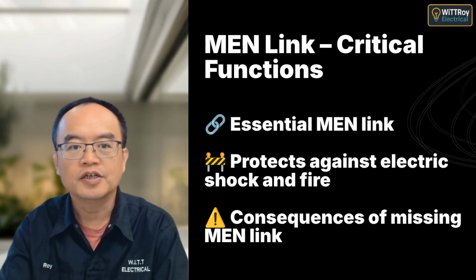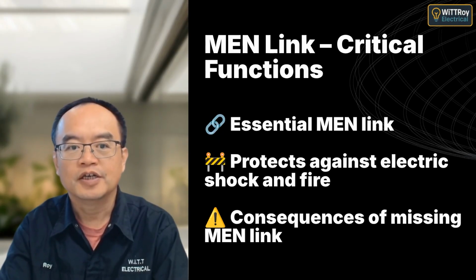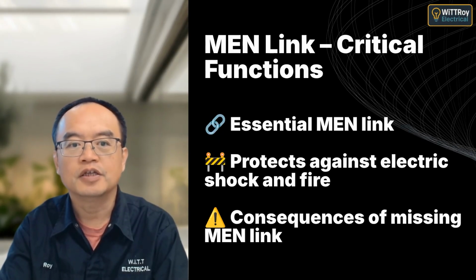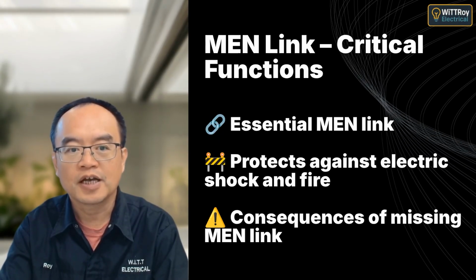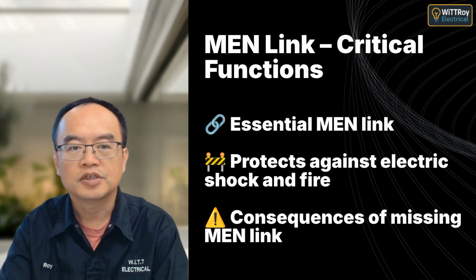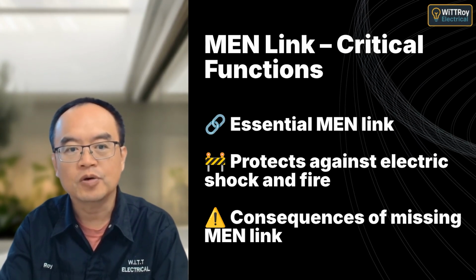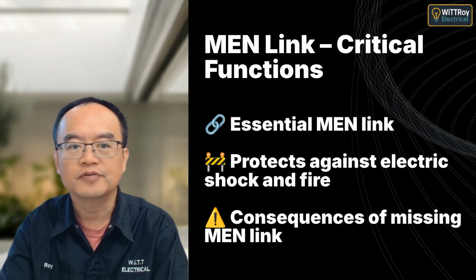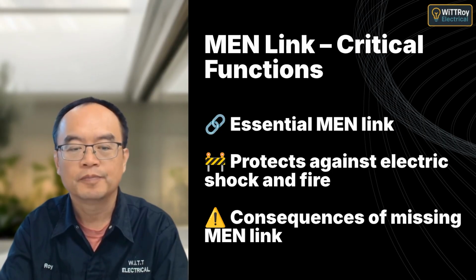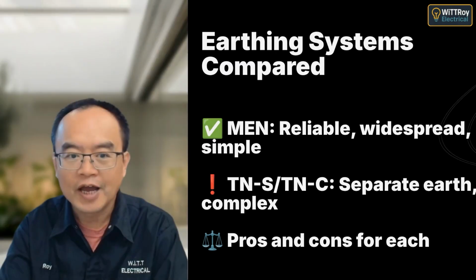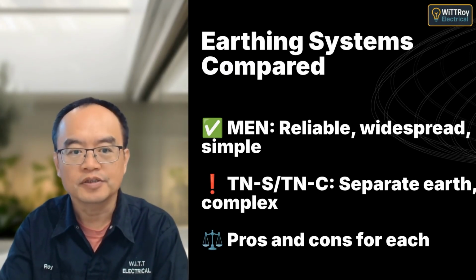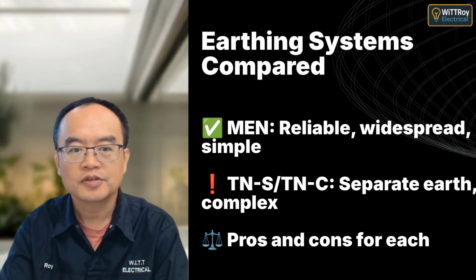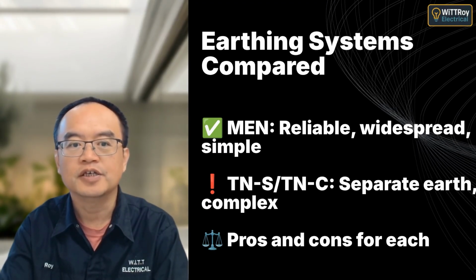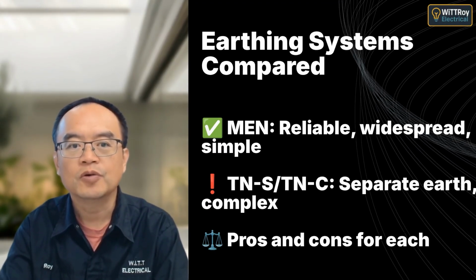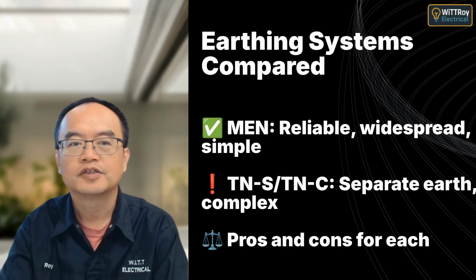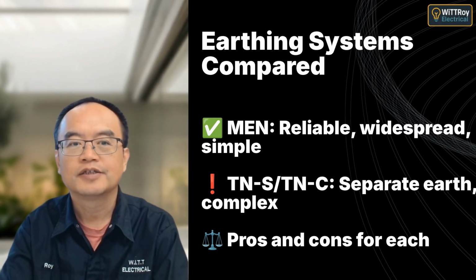The MEN link is crucial. It provides protection against electric shock and fires. Without it, installations can experience dangerous voltage levels, improper earth fault paths, and protective devices failing to operate correctly. MEN is popular due to reliability and simplicity. Alternative systems like TNS or TNC have separate earthing arrangements but involve more complexity. Each has its unique advantages and disadvantages.